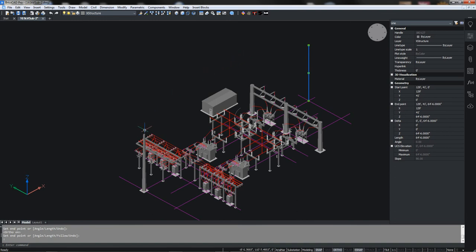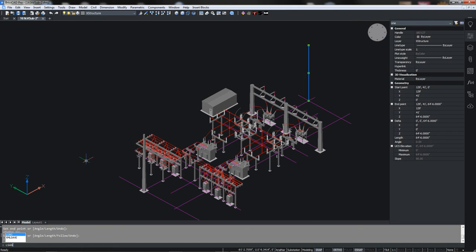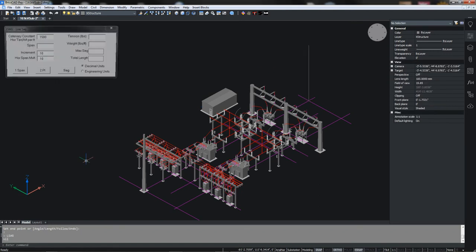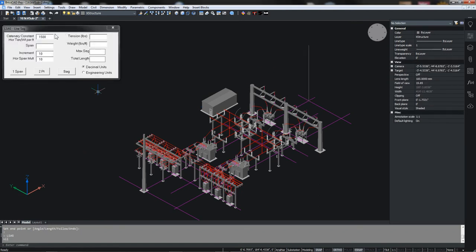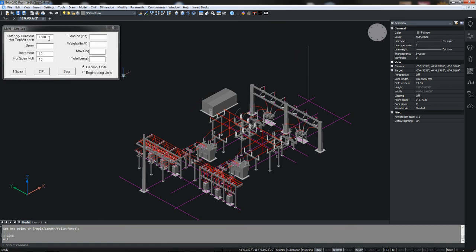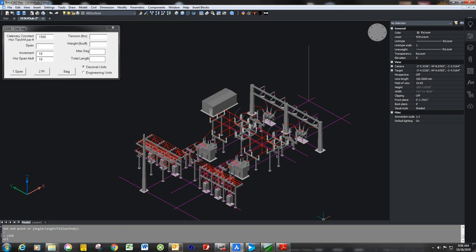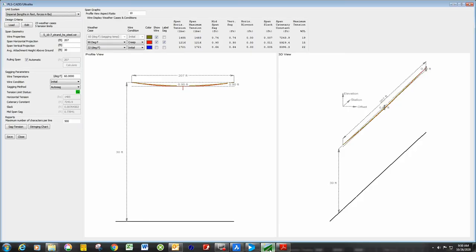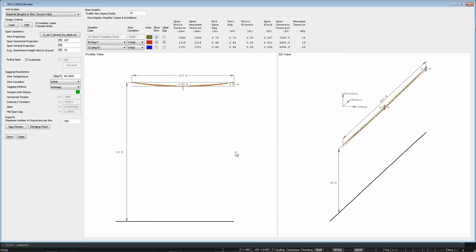With that, the next thing we want to do is put in our static. We could probably just draw a straight line between those two points, however I want to use a simple sag program that is based on the catenary constant, and it draws a catenary curve which is made up of a series of polyline segments between two points. The first thing we really need to know is a catenary constant, and you need to get that from a design program like Alcoa Sag 10 or in my case I'm using PLS-CADD/Ultralite, which is a free application that gives us the information you can get from Sag 10.